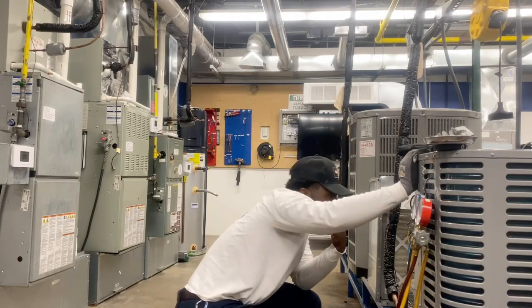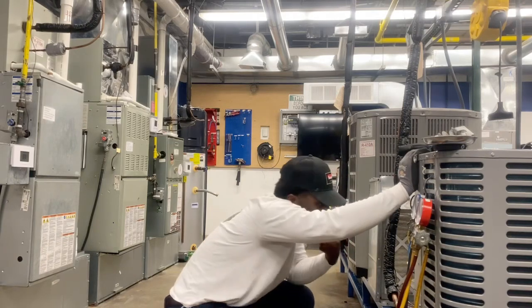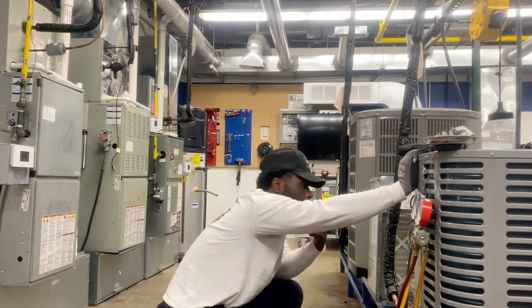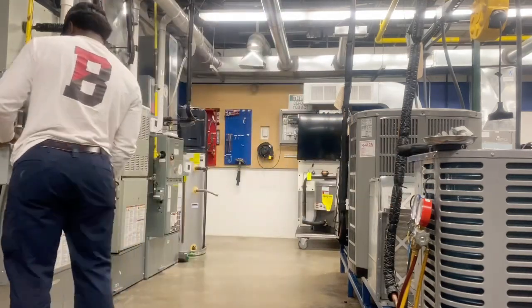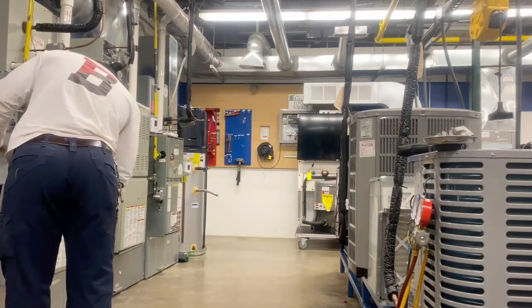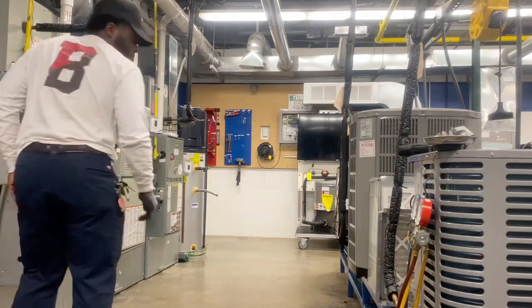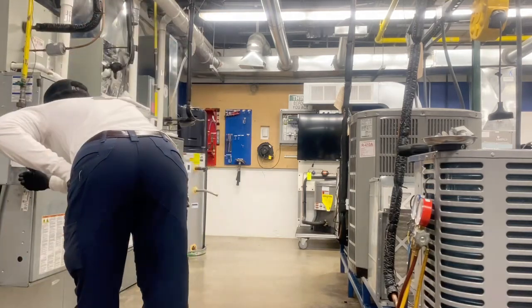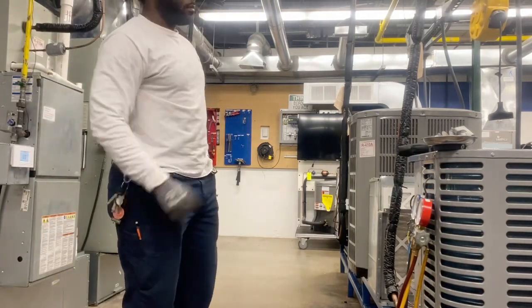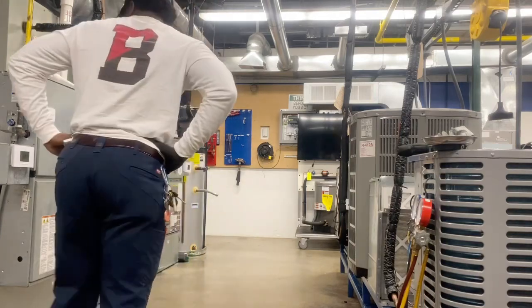In this system was a dual run capacitor, so that's like two capacitors in one. One is rated for 35 microfarads and the other for 5, for the fan. The 35 is for the compressor. Now let's kick it back on and see what the pressures end up looking like.